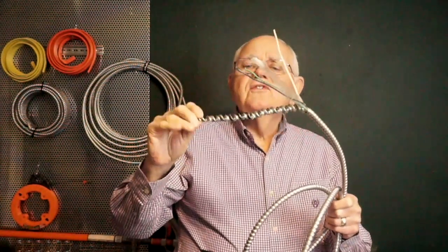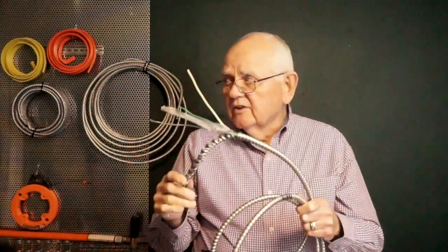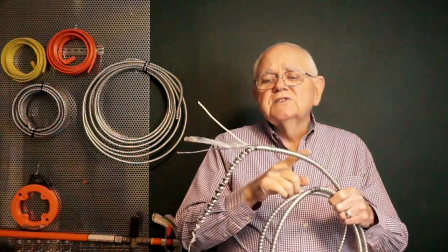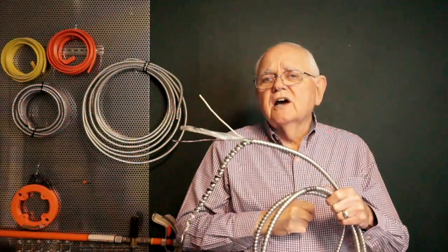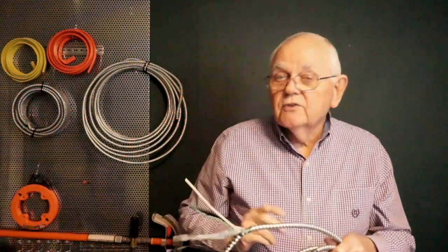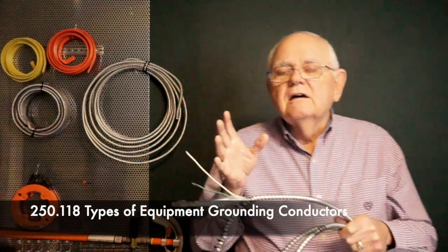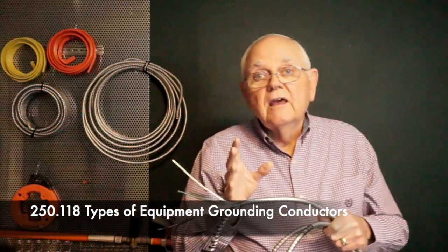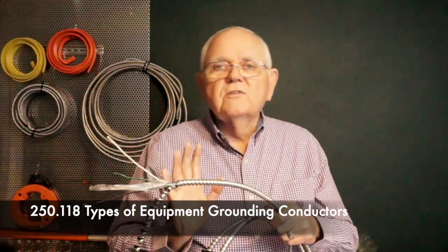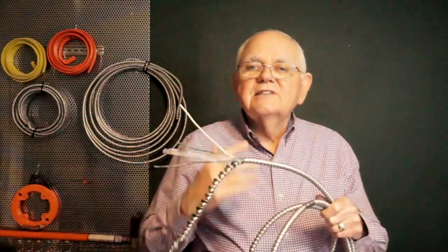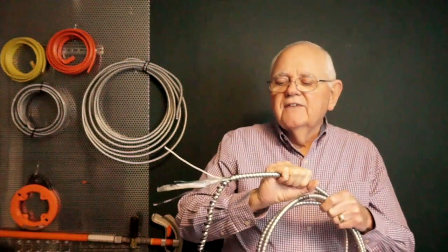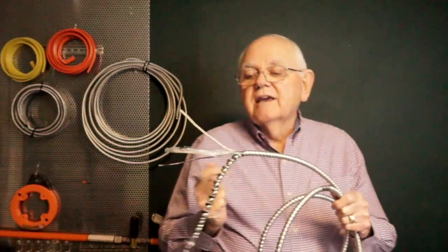Now, let's see, equipment grounding conductors. Let's talk about that. We said it's probably not a good idea to use this interlocking metal tape as an equipment grounding conductor, is it? However, we said that we could use maybe the other two types. To find this information, we go back to Article 250 on grounding and bonding, specifically 250.118. 250.118 tells us the types of equipment grounding conductors we can use. In fact, 250.118 item number 10 talks about MC cable. And it says that there are only 3 cases where we can actually use metal-clad cable as an equipment grounding conductor.